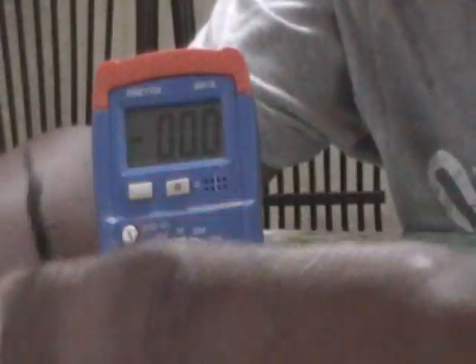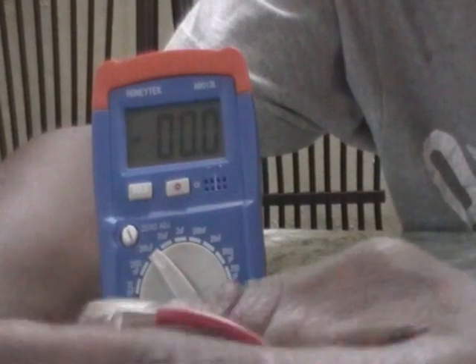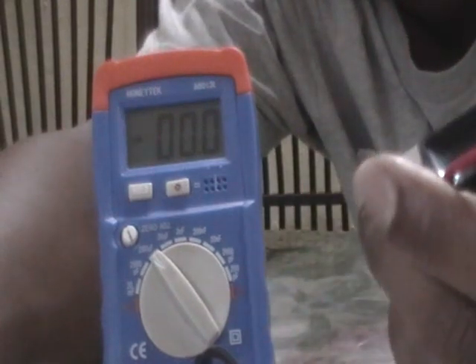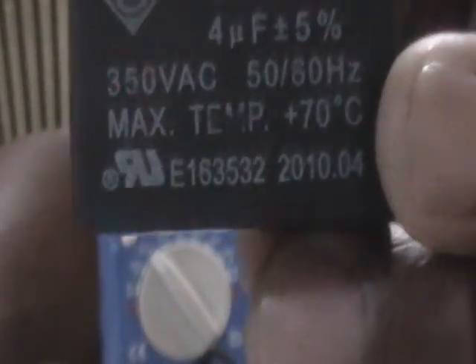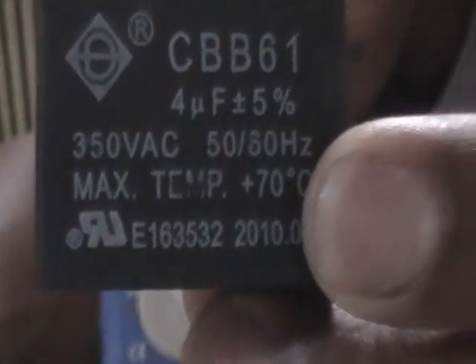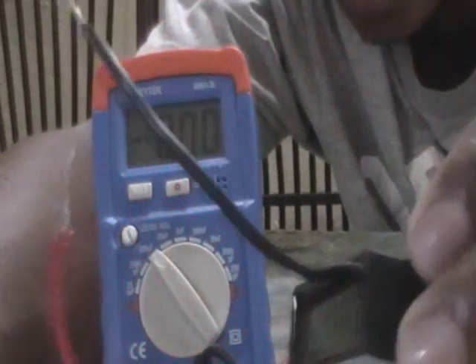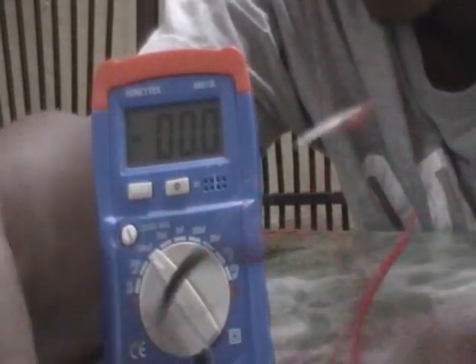This last capacitor I got out of the industrial cooling fan. It's also rated at 4 micro farads, but 350 volts AC, with a maximum temperature rating of 70 degrees C and a part number below. Now, this is also a non-polarized capacitor — even though you see red and black wires, you don't have to match them up. I'm going to put red to the black lead to show you it doesn't matter; there's no polarity here.